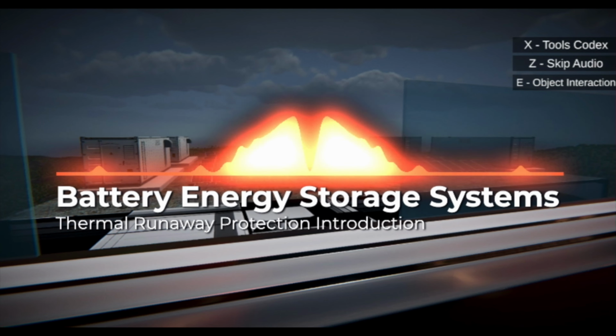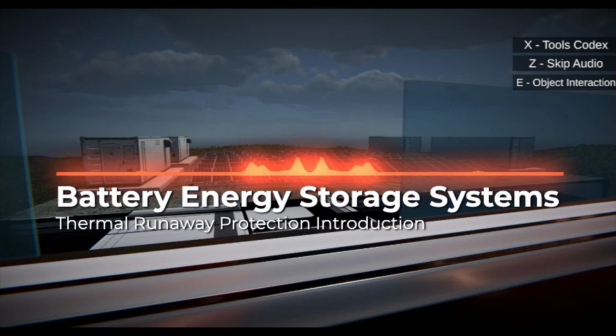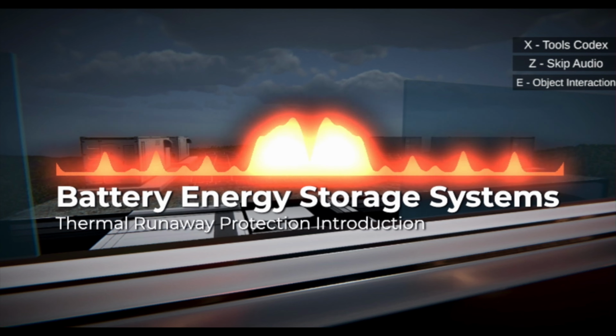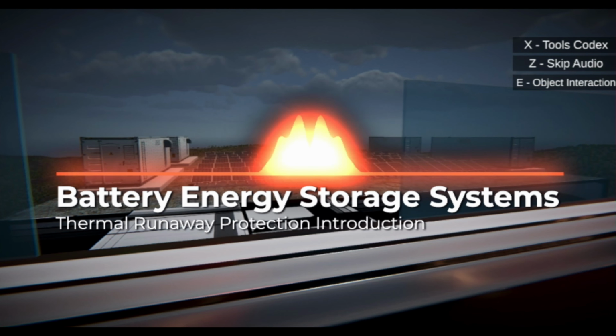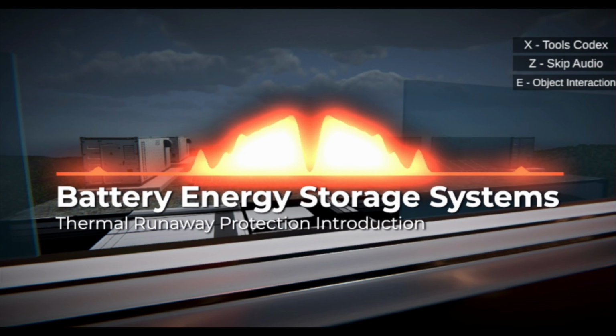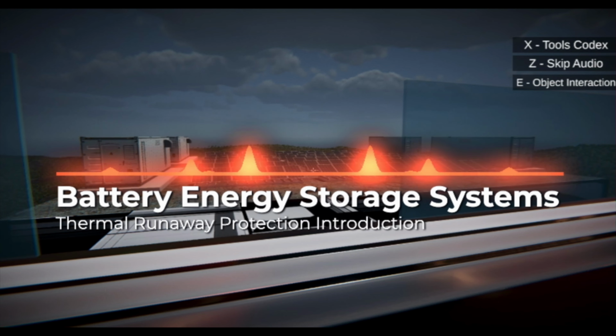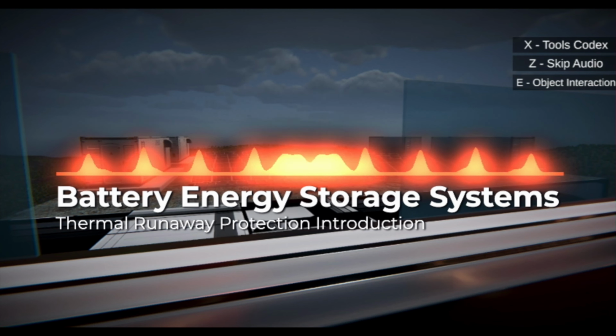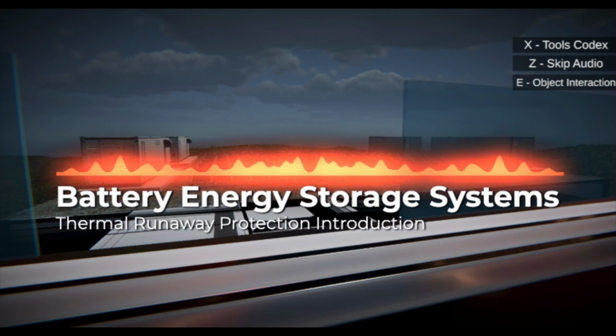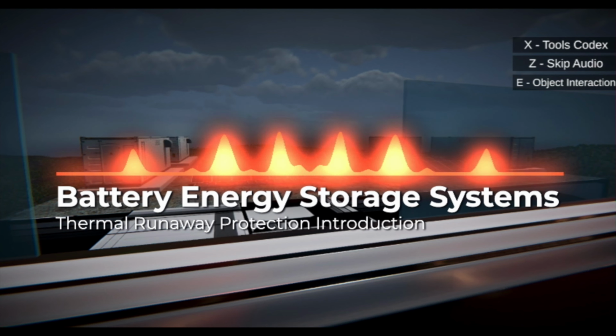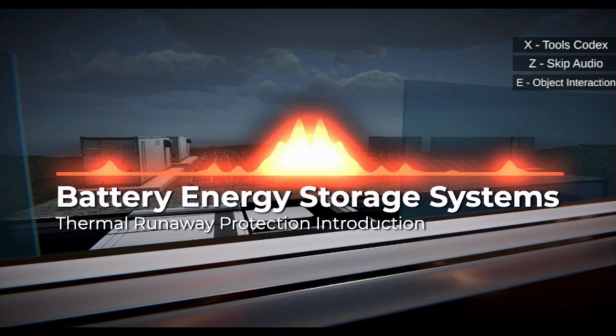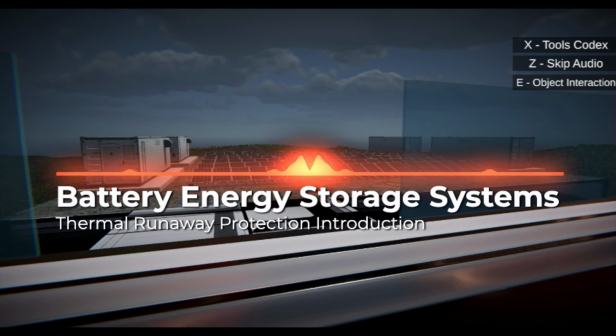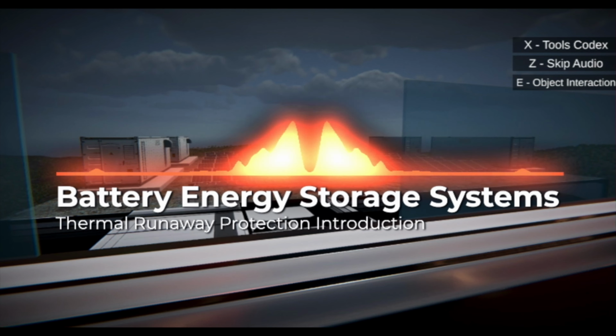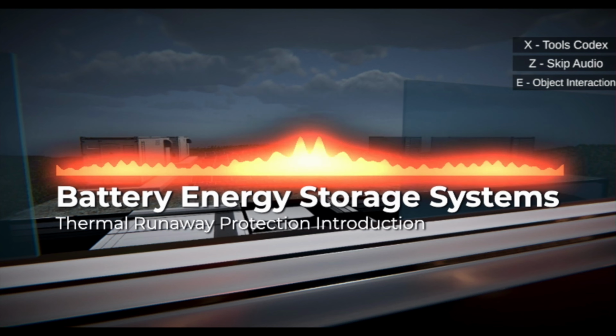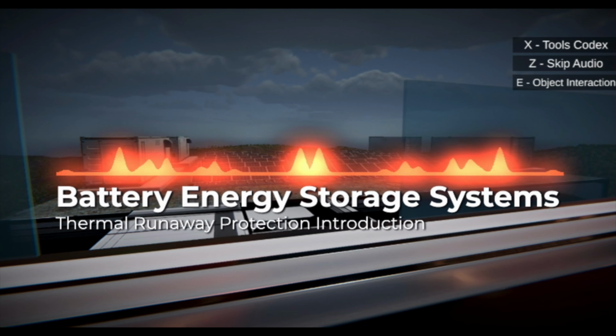Another critical NFPA standard that demands our attention is NFPA 855, which specifically addresses the installation of stationary energy storage systems. NFPA 855 encompasses a comprehensive set of requirements that span multiple disciplines, including fire protection, ventilation, electrical equipment specifications, and emergency disconnecting means. This standard provides essential guidance on critical aspects, such as the selection and installation of fire suppression systems, ventilation design considerations, electrical equipment requirements to ensure safe operation, and the establishment of emergency disconnecting means for rapid shutdown in hazardous situations. Adherence to NFPA 855 is indispensable to ensure the utmost safety in BESS installations and mitigate potential hazards that may arise.